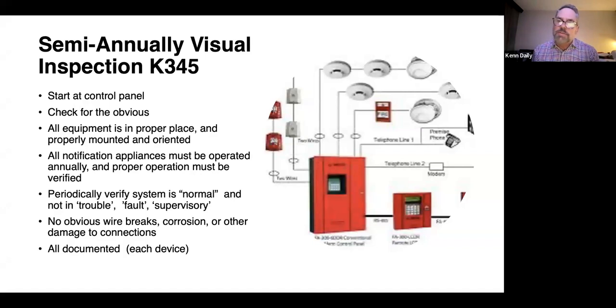But the idea is that they look at the whole system, and this, of course, would be the most basic. Make sure that the system's normal. I would just tell you to go look at your system and make sure it's operating normally. There's no fault or supervisory signals. Once you have any kind of signals on that, you must repair those. You must act immediately to fix that. That's like your internal QA process. And if you see one of those faults or supervisory signals, you have to get that fixed absolutely post haste. You're required to react quickly.